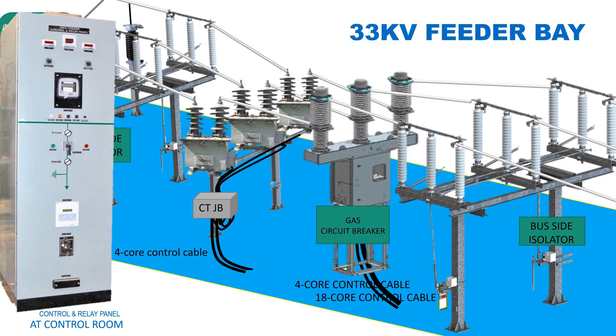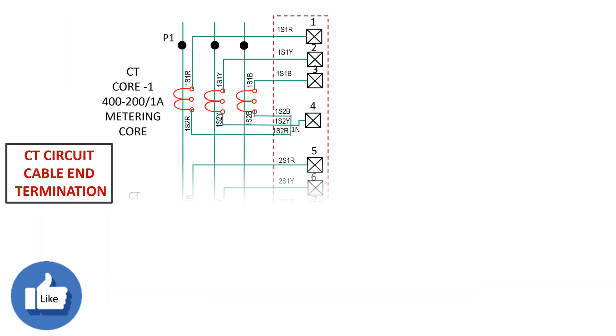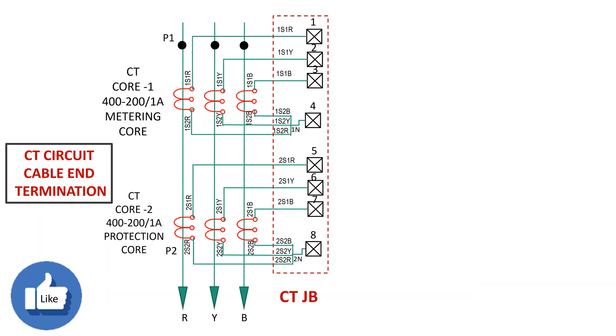There are many terminal blocks at the CT junction box, circuit breaker mechanism box, and at the control and relay panels. We have to make a termination schedule by which we can connect all these components with their respective terminal blocks by labelling the cable at both ends. First, check the drawing for both ends of the components to be connected. Suppose we are going to make a termination schedule between CT terminals and control and relay panel terminals for the same feeder.